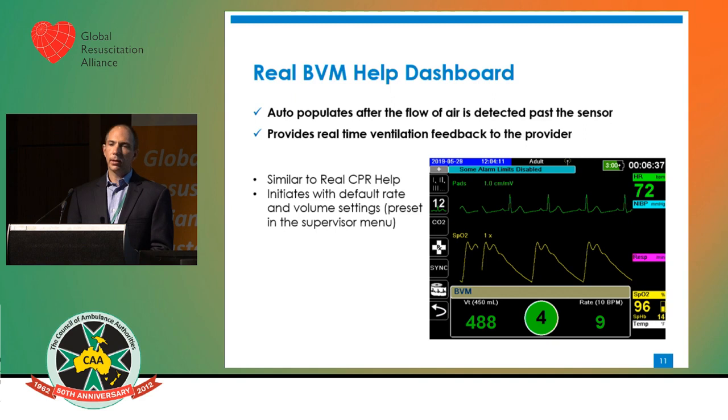And attaching that is going to get you this dashboard. It takes a single breath to initiate the dashboard. As you start to ventilate, that dashboard appears, and if you look, you've got target volume, target rate, delivered volume, delivered rate, and then a countdown timer in the middle that is going to ideally time the provider to deliver that appropriate rate. So real-time volume and rate feedback on the screen, breath to breath.